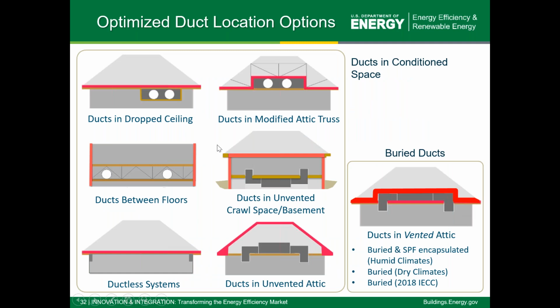The optimized duct locations called out in the program specs as viable solutions are shown here. Six of them, on the left side, are different strategies where ducts are located in conditioned space, and most of these probably look familiar: a drop ceiling creating a pocket in the modified attic truss—several Habitat affiliates in Florida have used that design in the past; ducts in an open web floor truss between floors; an insulated, air-sealed, unvented crawl or basement, which is always a good spot to locate ducts as well as equipment; ductless HVAC systems; and ducts in an unvented attic. Those are all good viable solutions.